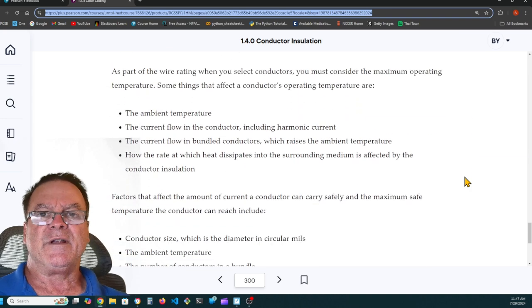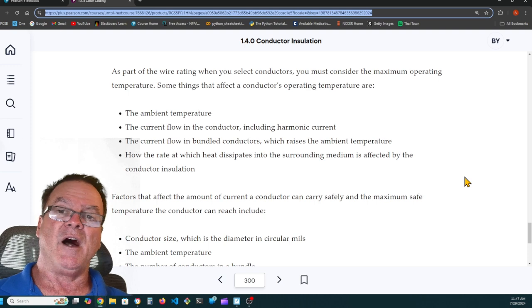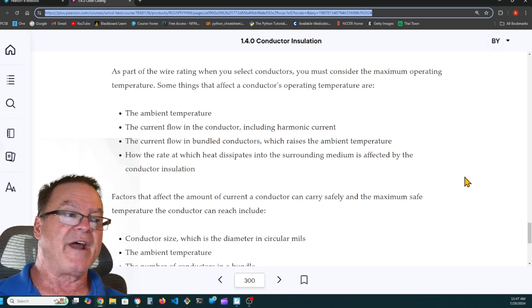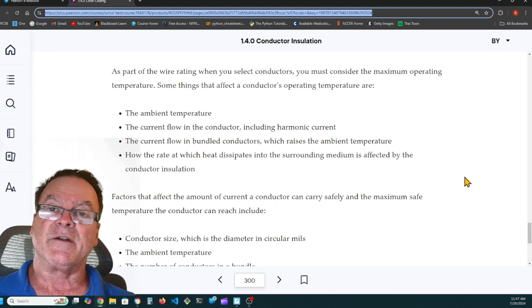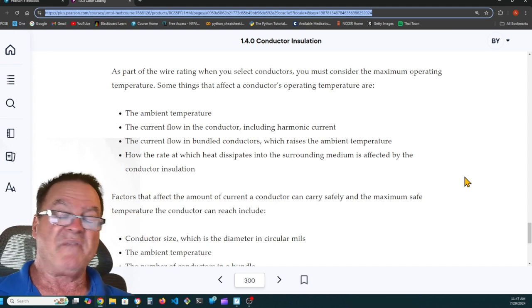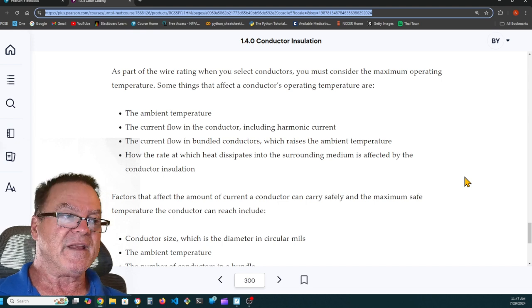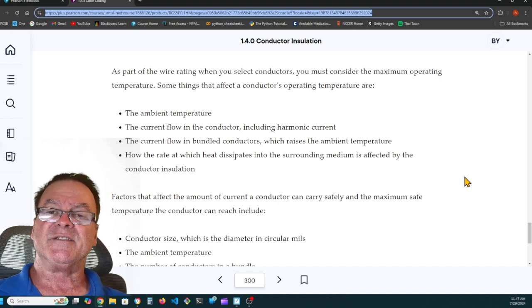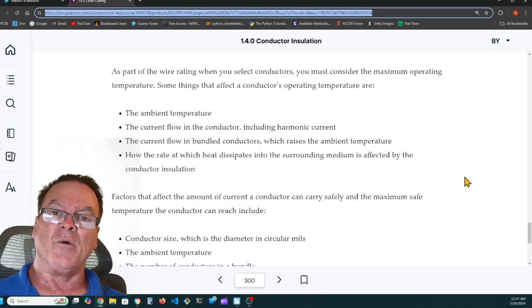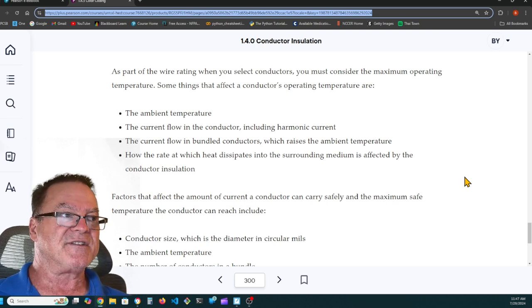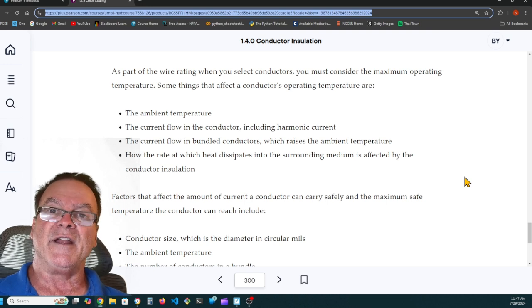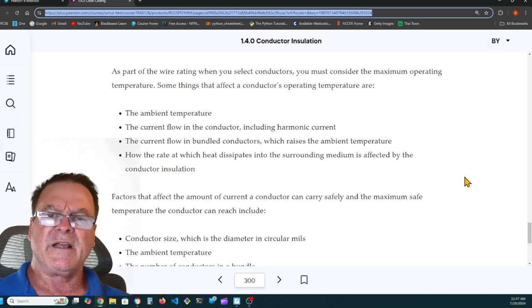The heat isn't going to bother the copper. Copper is copper. So if you have a wire that's good for 90 degrees Celsius and it's copper, or you have a wire that's rated for 60 degrees Celsius copper, that copper is the same copper. It's the insulation that makes it good for 60 degrees Celsius or 75 degrees Celsius or 90 degrees Celsius. If you have a 60 degrees Celsius rated wire and you're putting 90 degrees Celsius of temperature on it, that insulation is going to bake.